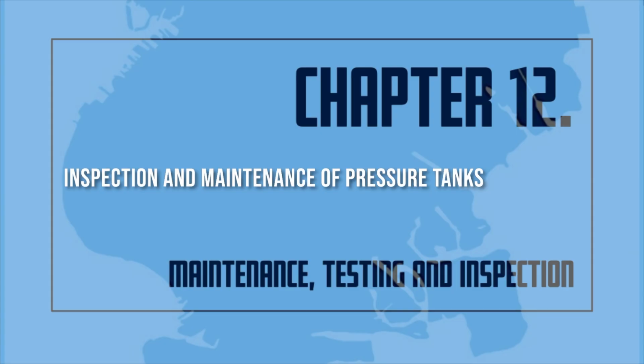The inside of pressure tanks shall be inspected carefully every 3 years. Rusting in the tank may require repainting or other repairs. The inside of the tank should be thoroughly scraped, wire brushed, and repainted. No foreign materials should be allowed to fall into the sprinkler system. The temperature inside the structure housing the pressure tank should be checked daily during cold weather to make sure that the temperature is at least 40 degrees Fahrenheit at all times.